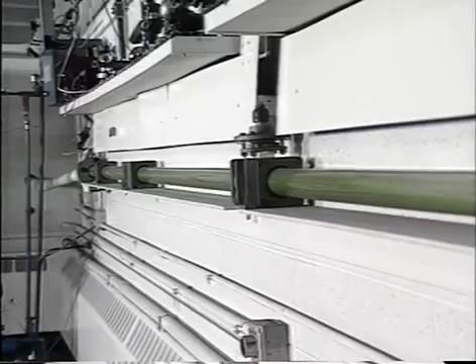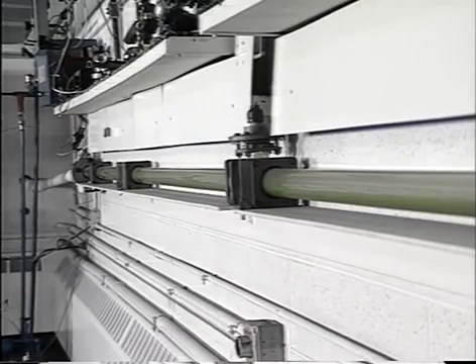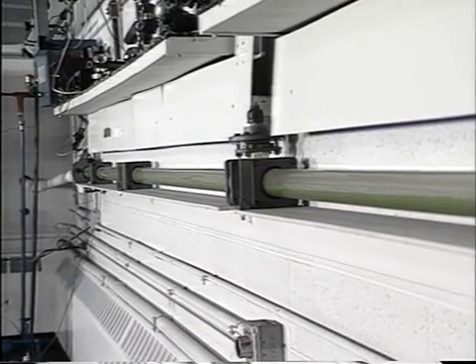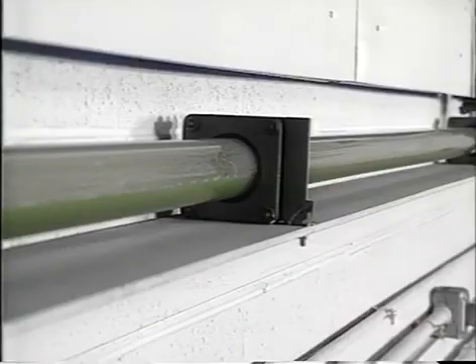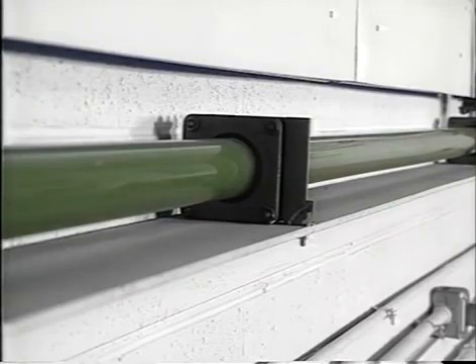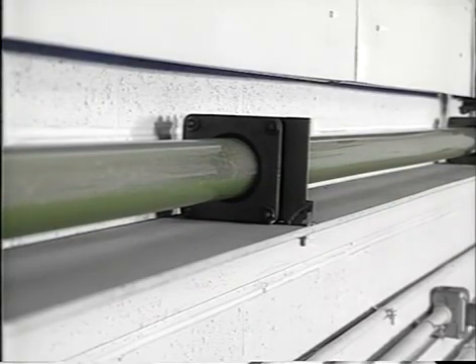Observe now as the compressed air flow increases. The waves formed on the surface of the condensate become higher. Further increasing the air flow causes the waves to block off more of the cross section of the piping until a seal is formed, completely closing off the pipe. A slug of condensate is accelerated downstream by the pressure differential, becoming a piston that gains in mass and velocity as it travels.